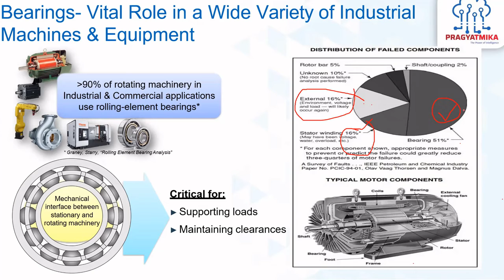Why am I discussing this? Whenever you are designing solutions for your Industry 4.0, and you are taking care of any monitoring element, for whatever machine or process you are monitoring, you will have to justify which component you need to monitor continuously, based on which you can give a better prediction about performance and failures. We could have monitored just the voltage and temperature, but that has only a 16% impact. We could have monitored only the windings condition, but it has only 16% impact. But if I monitor the bearing, that has a 51% impact on the life of the motor. That's why these things need to be taken care of: which component has the most chance of failure, and that requires continuous CBM, continuous monitoring.